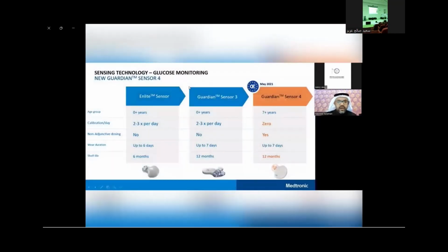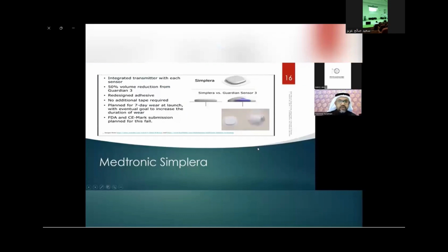So these are the Guardian Medtronic sensors. As you can see, the Guardian Sensor 4, which just recently became available in Saudi Arabia, has a shelf life of 12 months. We always had a problem with the previous sensors, which had a shelf life of less than 12 months. But also, the beauty in this new sensor is that it does not require calibration, which actually showed us that it has much better accuracy, and it lasts up to 7 days, like the previous one, but it's approved for 7 years or older. What is going to come in the future?